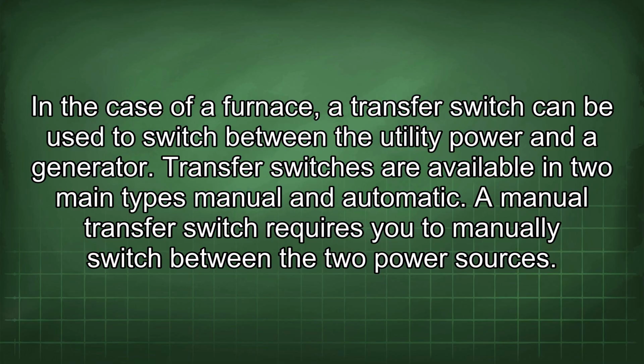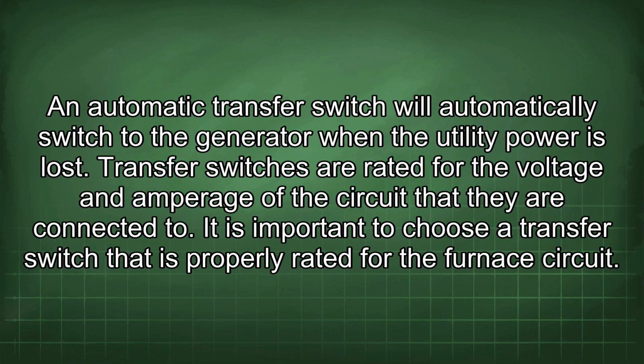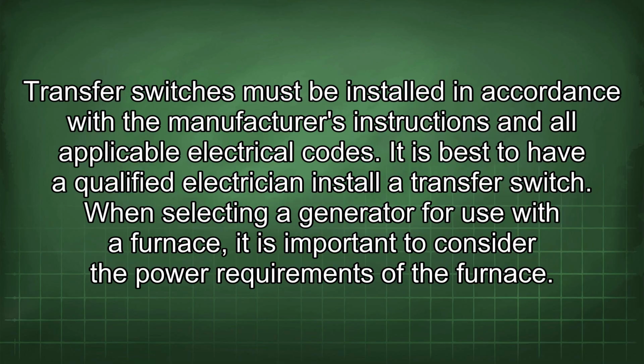Transfer switches are available in two main types: manual and automatic. A manual transfer switch requires you to manually switch between the two power sources. An automatic transfer switch will automatically switch to the generator when the utility power is lost. Transfer switches are rated for the voltage and amperage of the circuit that they are connected to. It is important to choose a transfer switch that is properly rated for the furnace circuit. Transfer switches must be installed in accordance with the manufacturer's instructions and all applicable electrical codes. It is best to have a qualified electrician install a transfer switch.